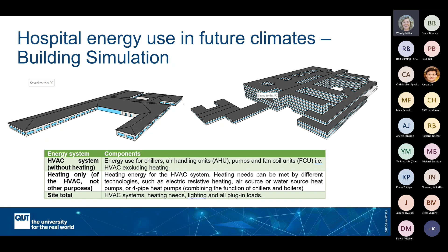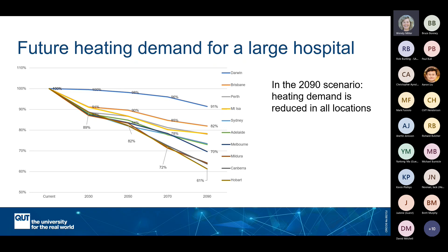So what have these models shown? This slide uses 2022 as the baseline and shows the reduction in future heating demand in all locations for the large hospital. For example, it shows that in Hobart, by 2090, the heating load required by that large hospital will be about 61% of what the current heating load is. So all zones, all locations, see a reduction in heating demand.